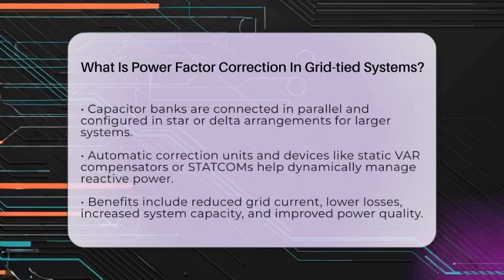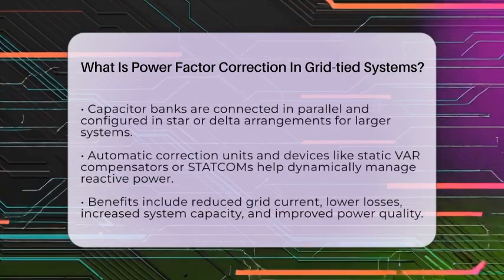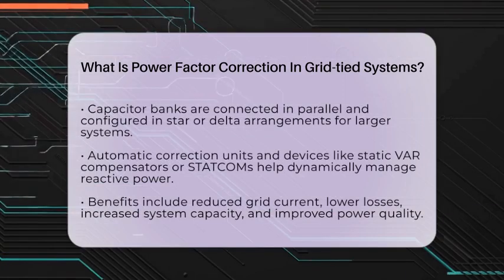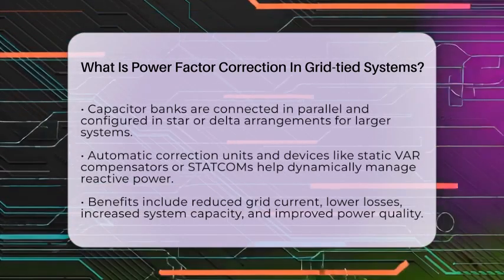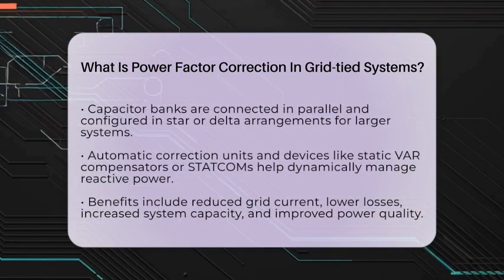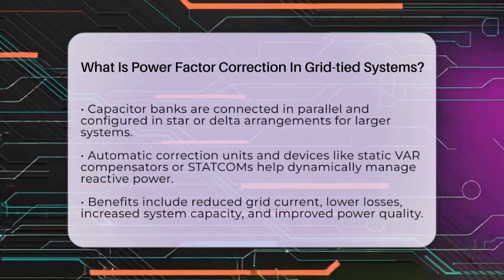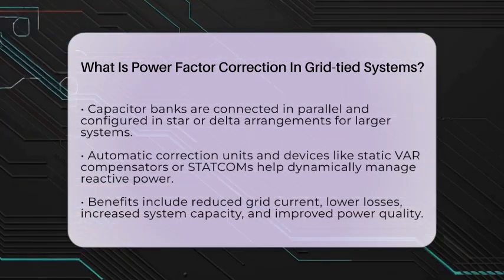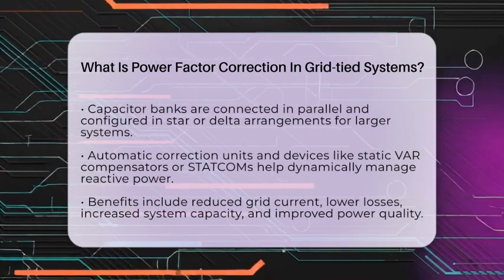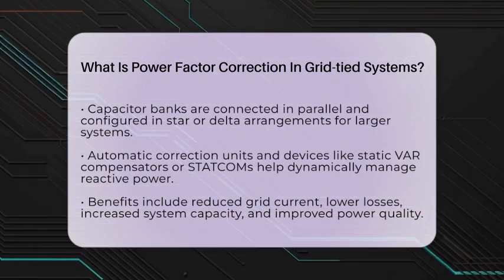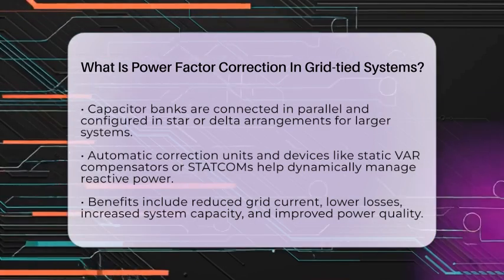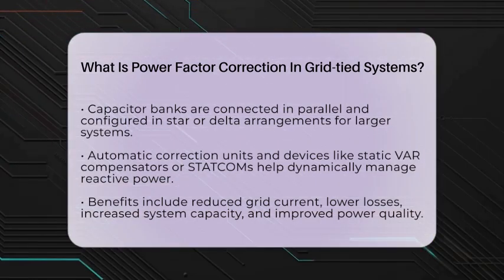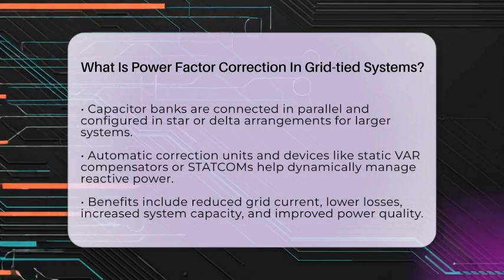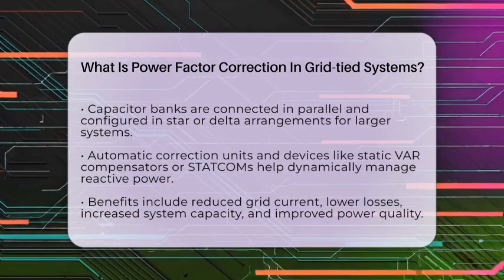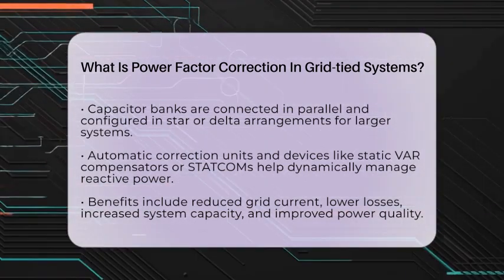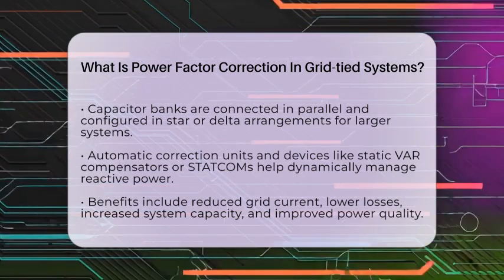In larger systems, such as industrial renewable installations, these capacitors are connected in star or delta configurations to balance the reactive power across all phases. Automatic power factor correction units can switch capacitors on or off depending on the load, making the system more dynamic and responsive. Some systems also use synchronous condensers or modern power electronic devices like static VAR compensators or STATCOMs to provide reactive power support quickly and efficiently.